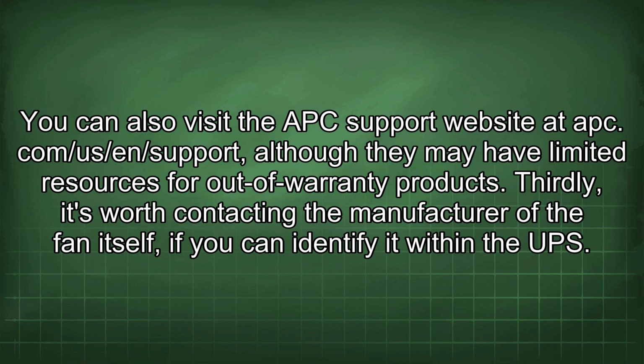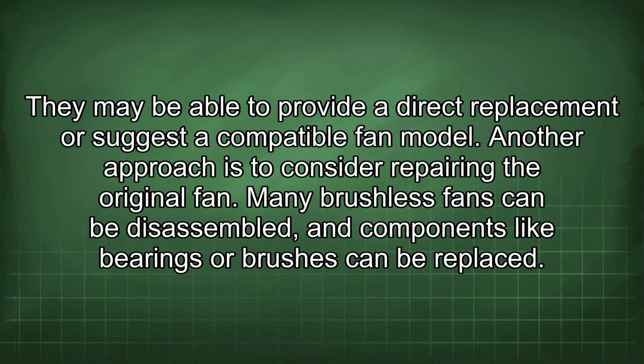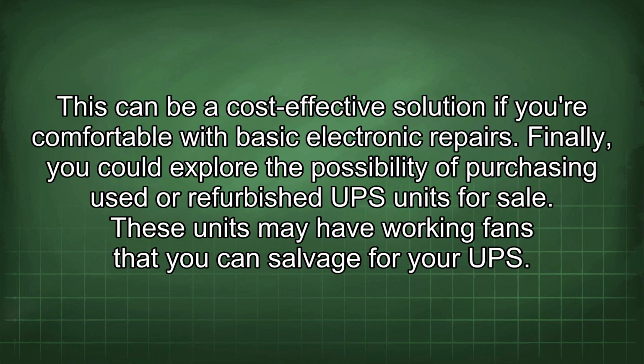Thirdly, it's worth contacting the manufacturer of the fan itself if you can identify it within the UPS. They may be able to provide a direct replacement or suggest a compatible fan model. Another approach is to consider repairing the original fan. Many brushless fans can be disassembled, and components like bearings or brushes can be replaced. This can be a cost-effective solution if you are comfortable with basic electronic repairs. Finally, you could explore the possibility of purchasing used or refurbished UPS units for sale. These units may have working fans that you can salvage for your UPS.